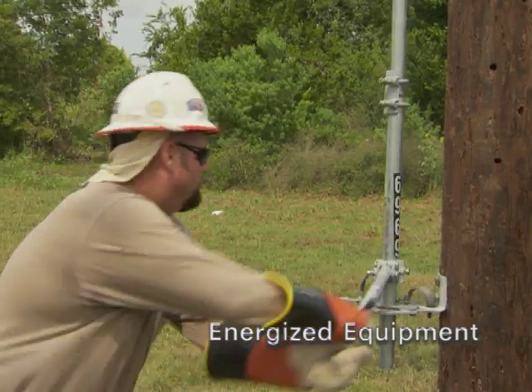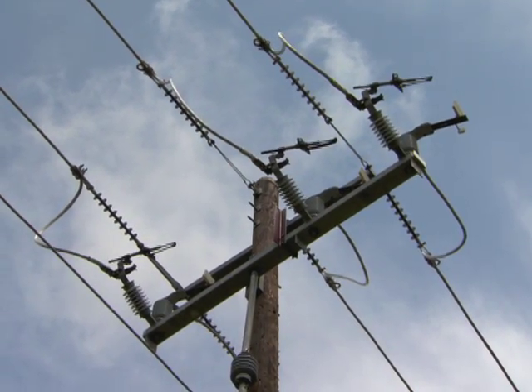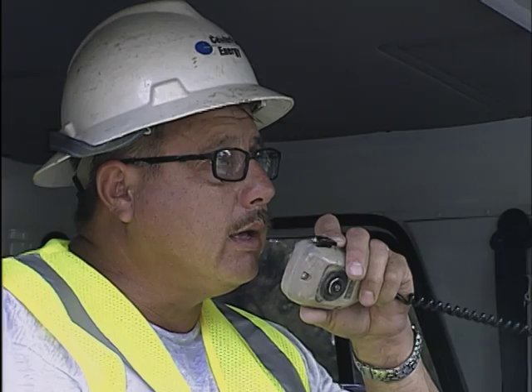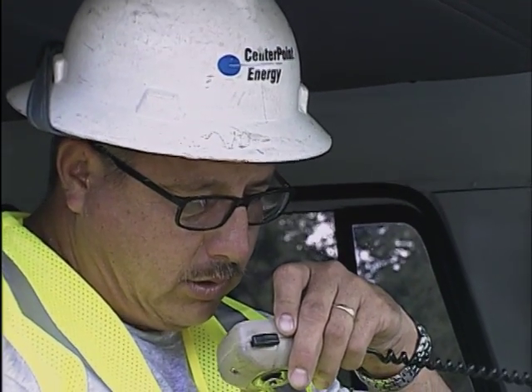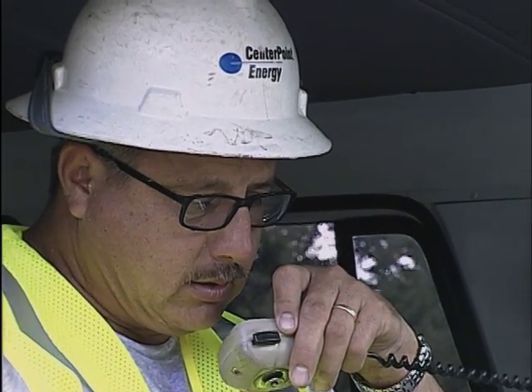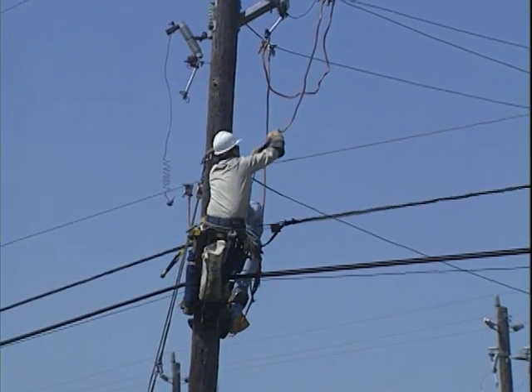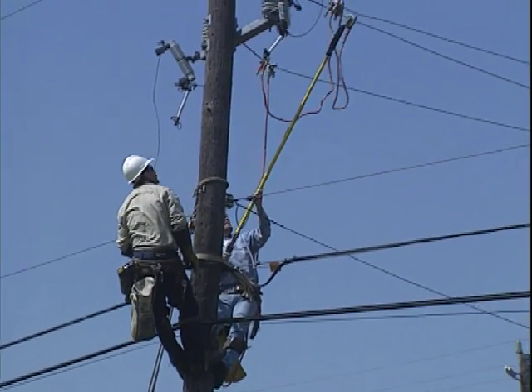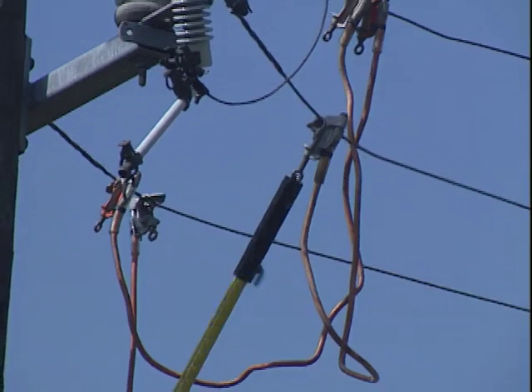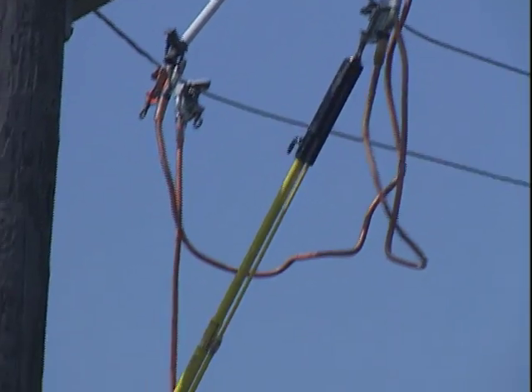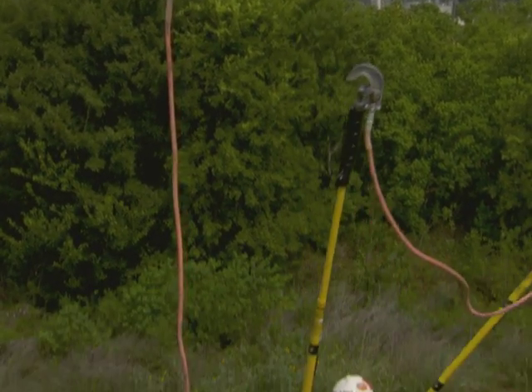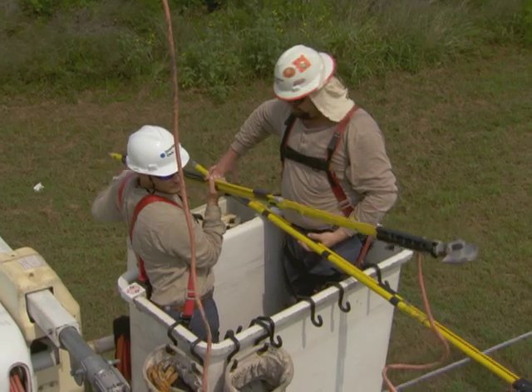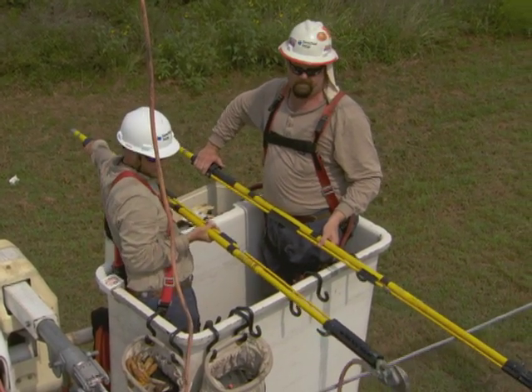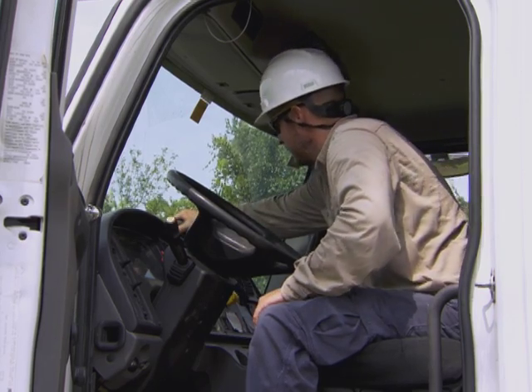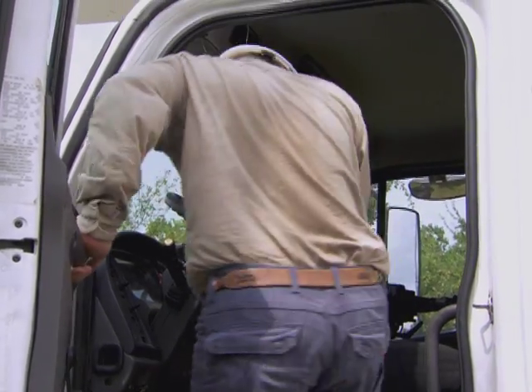Energizing feeder circuits must be done through your coordinator. Your coordinator will secure a switching order before opening or closing any gang-operated switches. Fused laterals can be energized only after the following steps have occurred. You have ensured that the equipment is capable of being energized and will not create a hazardous condition. All grounds have been removed and all personnel are aware that the line is about to be energized. Your coordinator has been notified and assured that these steps have been taken.